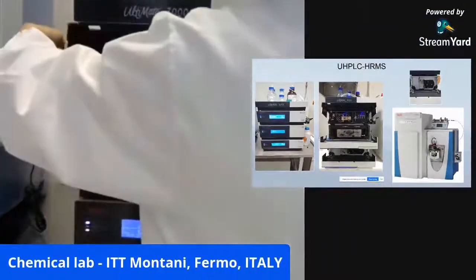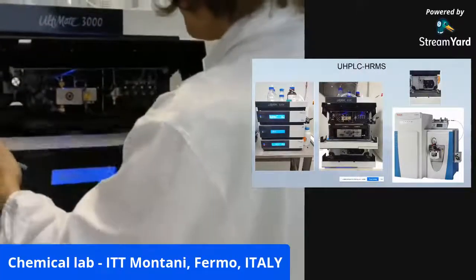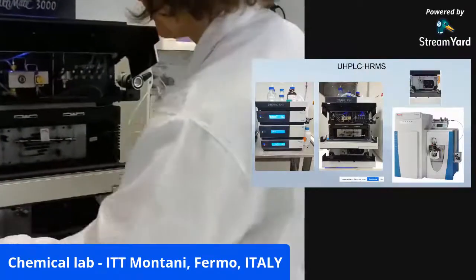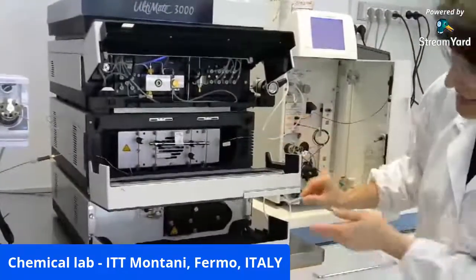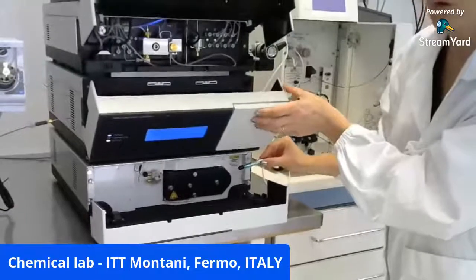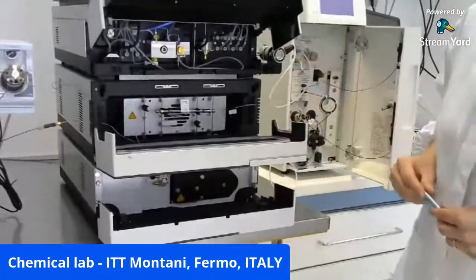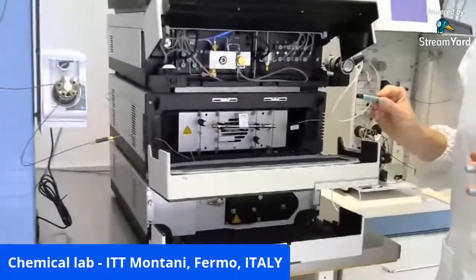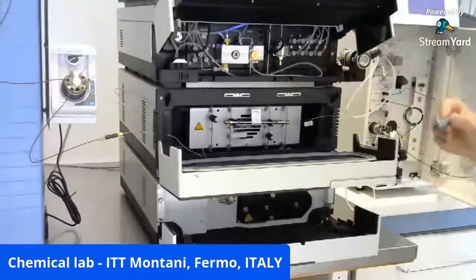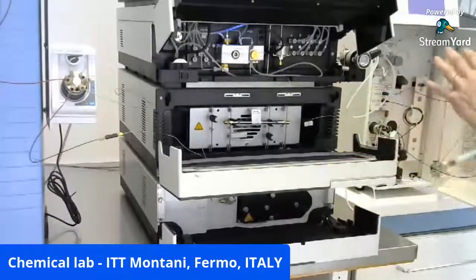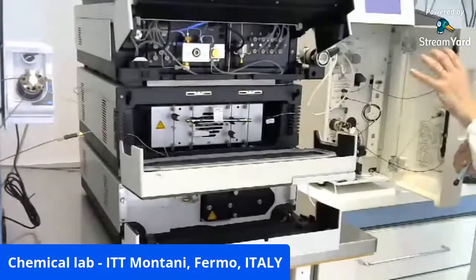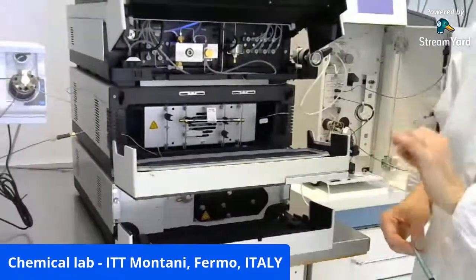This is the hydraulic circuit of an ion chromatograph that, as I told you before, is useful for analytes, for drugs which have an acid-base chemistry. Now I would like to show you the UHPLC with the column compartment, the pump compartment, the column compartment, and below with the detector, diode array detector compartment. Let's start with the pump compartment here. Actually, I will go through this compartment very quickly because many parts are similar to the ion chromatograph hydraulic circuit, but there are some differences that should be emphasized.